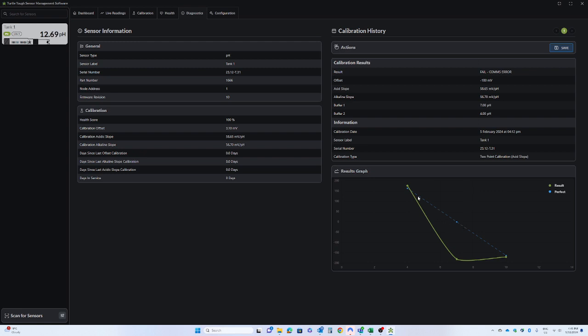This graph is particularly important. We can see the blue line indicates what a perfect sensor would look like, and you can see the results of my most recent attempt to calibrate a sensor. Here I accidentally used the same buffer twice, and I got a very distorted slope, which is the green line. As a result of that, we actually ended up with a failed calibration, and because it was outside the standard thresholds, the sensor would not allow that calibration to be written to the onboard memory. So the software did its job there in preventing a complete upset in the measurement.